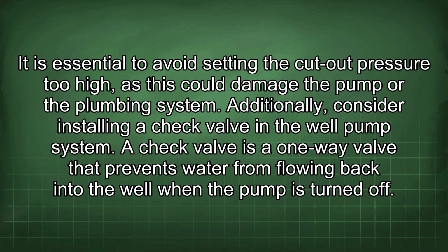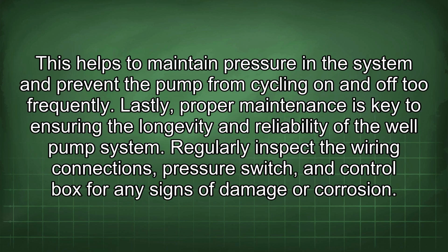Additionally, consider installing a check valve in the well pump system. A check valve is a one-way valve that prevents water from flowing back into the well when the pump is turned off. This helps to maintain pressure in the system and prevent the pump from cycling on and off too frequently. Lastly, proper maintenance is key to ensuring the longevity and reliability of the well pump system.